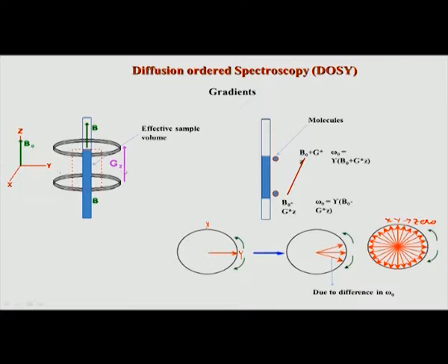Typically in all spectrometers, we have what are called Z gradients. We call it GZ, and that generates current in these coils, and if you put it in one direction, it will be an upward field towards B0, the main magnetic field, or if you do it in anti-clockwise or a different direction, it will be in the negative direction.